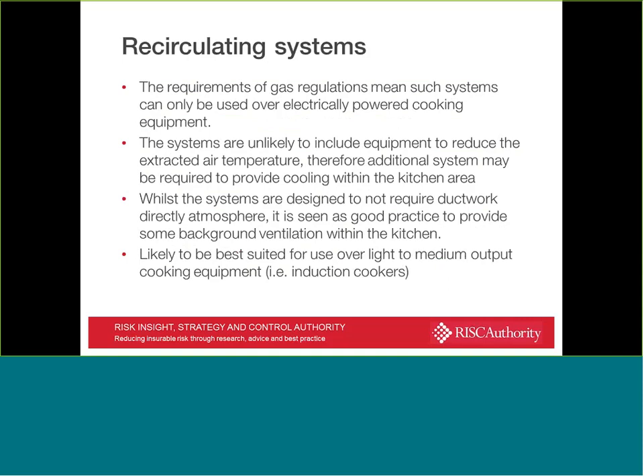And one of the systems I've looked at said that whilst they are designed to not require ductwork directly to atmosphere, it's seen as good practice to provide some background ventilation within the kitchen. In my view, they're suggesting that there should be a duct to the outside just in case. And they're likely to be best suited for use over light to medium output cooking equipment, for example, induction cookers.